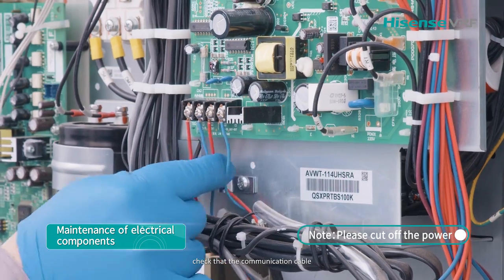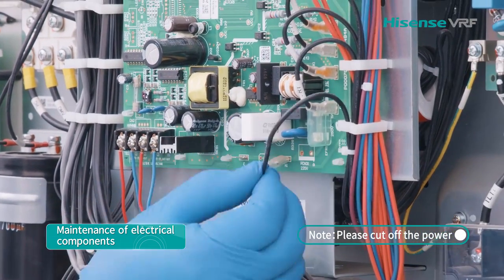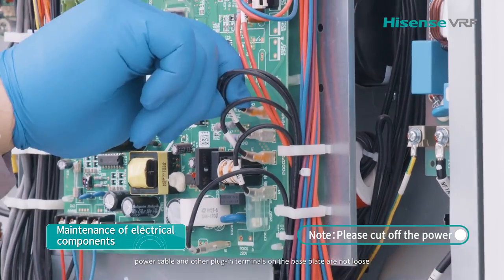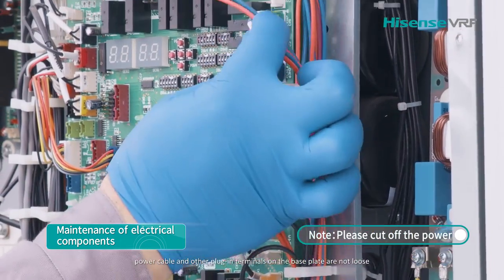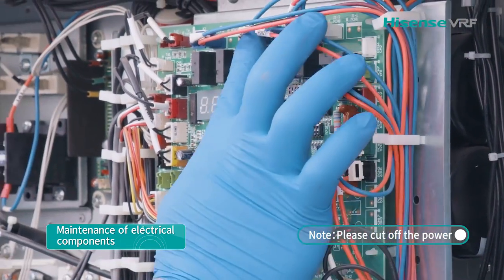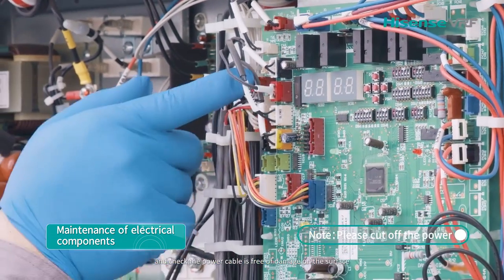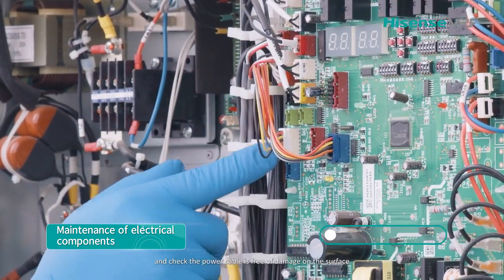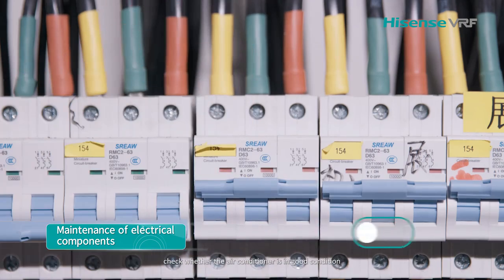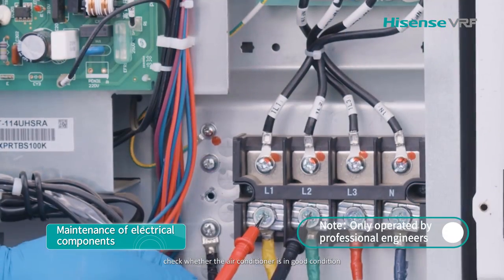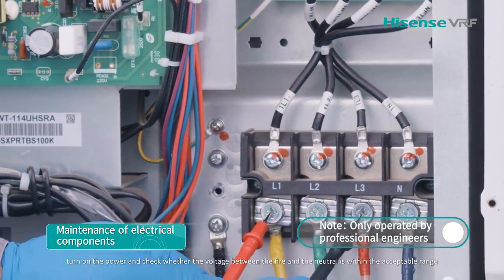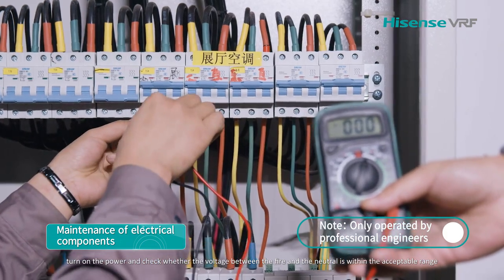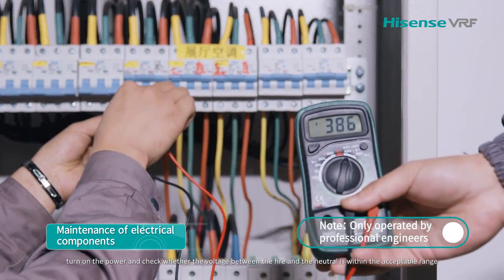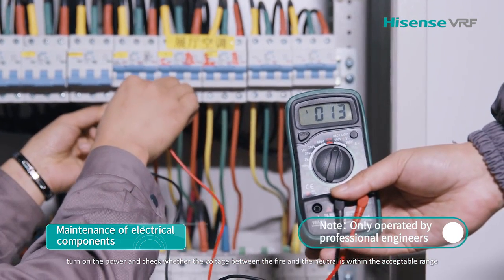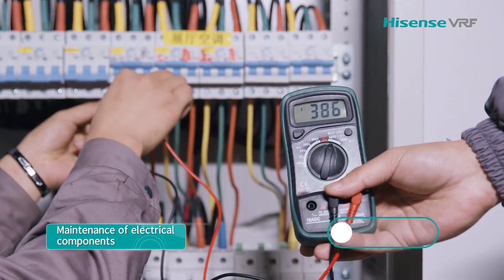Check that the communication cable, power cable, and other plug-in terminals on the base plate are not loose. And check the power cable free of damage on the surface. Check whether the air conditioner is in good condition. Turn on the power and check whether the voltage between the fire and the neutral is within the acceptable range.